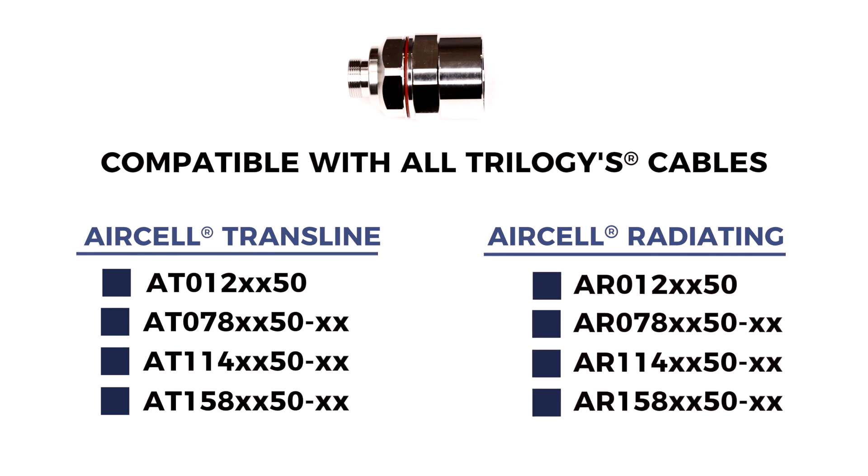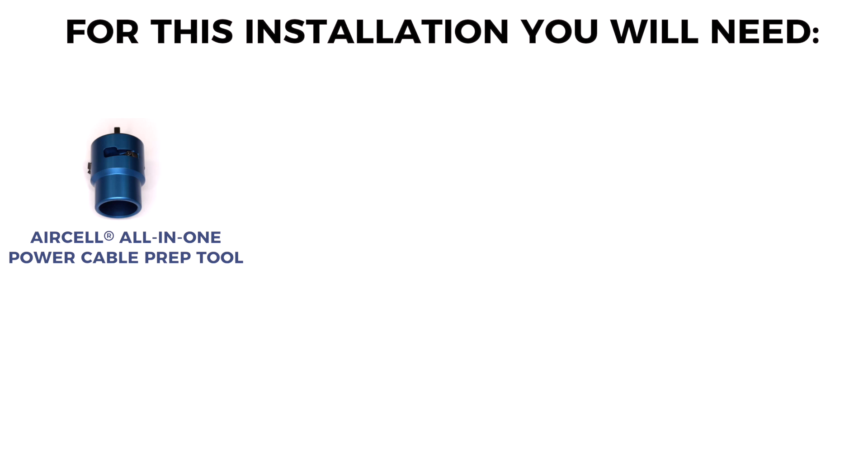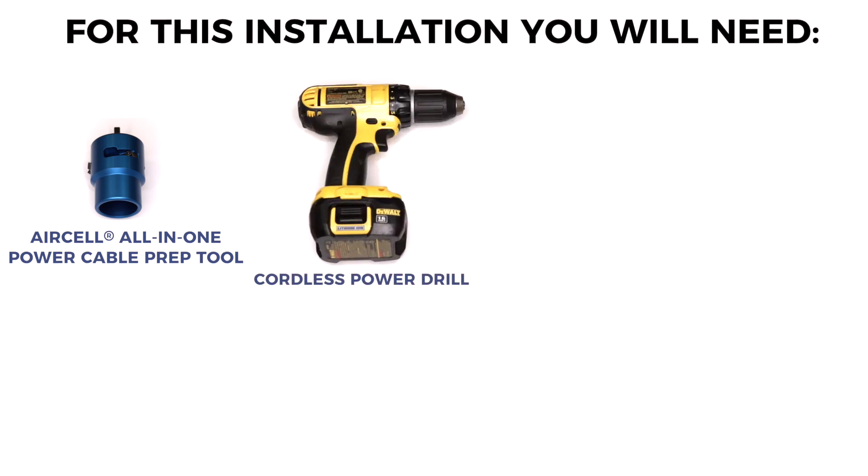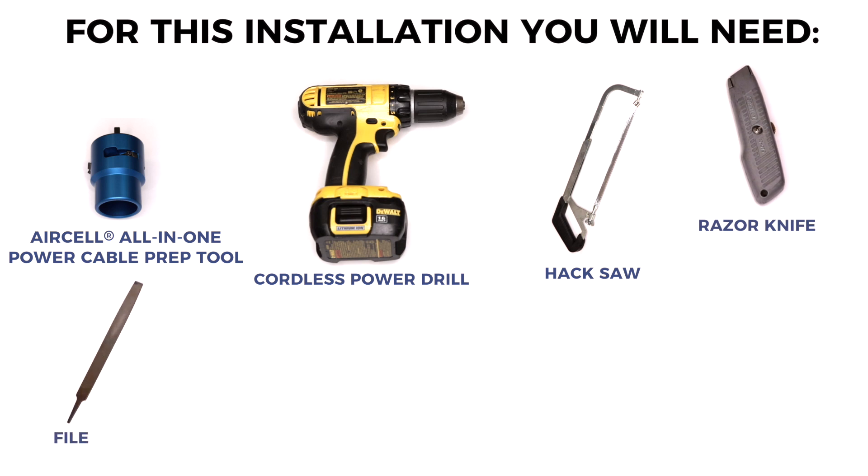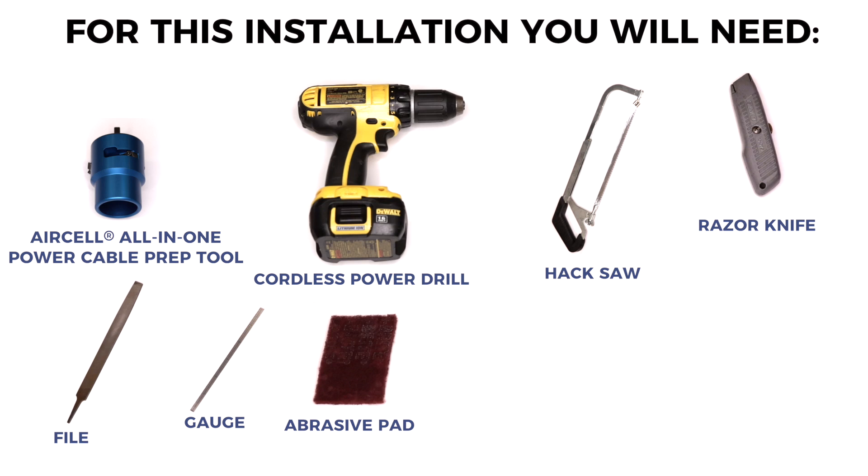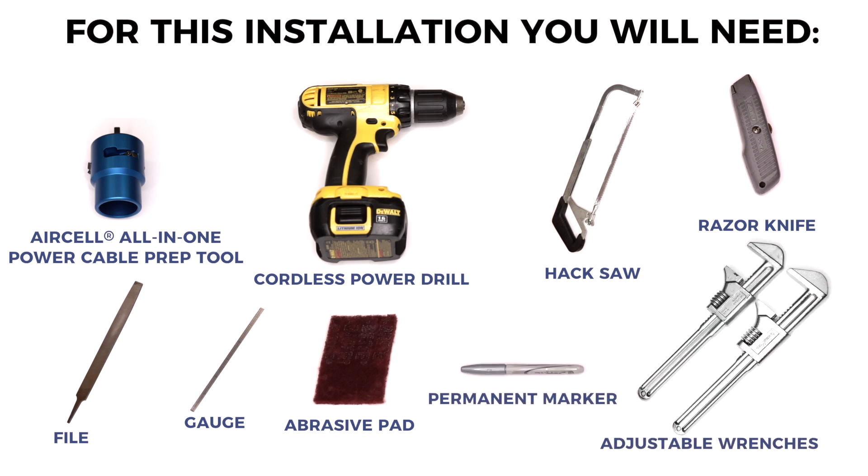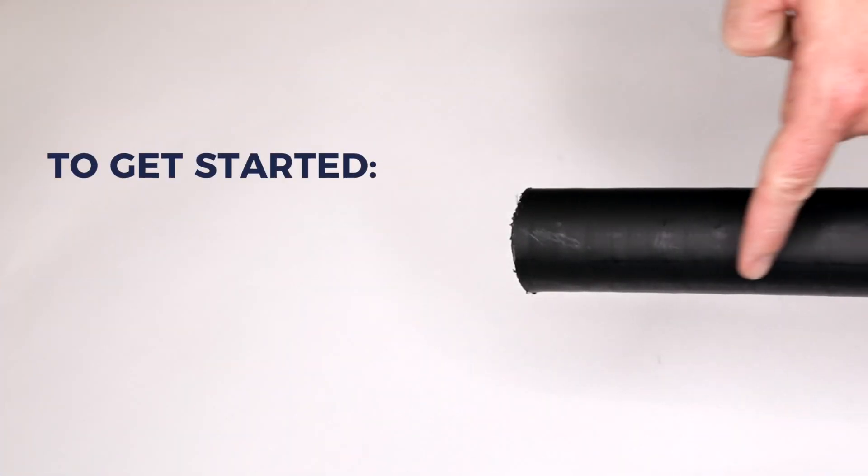For this installation you will need the AirCell all-in-one power cable prep tool, a cordless power drill, hacksaw, razor knife, file, small ruler or wire, abrasive pad, permanent marker, and adjustable wrenches. To get started, be sure to hold the cable at a downward angle throughout the entire process to avoid any shards or debris from entering the cable length.